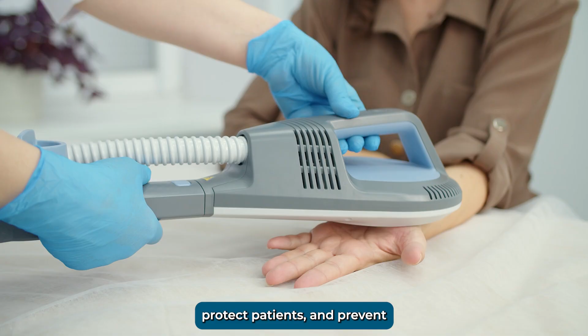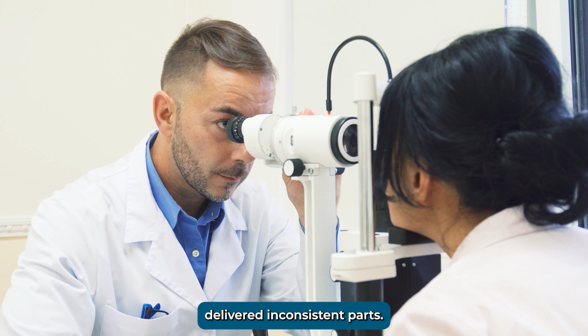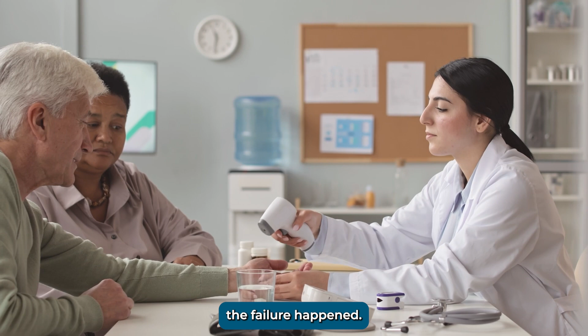The first mistake companies make is confusing the symptom with the root cause. A complaint says the device leaked, a test failed, a unit shut down, a sterile barrier broke. A supplier delivered inconsistent parts. Those are not root causes, those are signals. The real question is why the failure happened, why the process allowed it to happen, why inspection did not catch it, and whether the same weakness exists anywhere else in the product line.